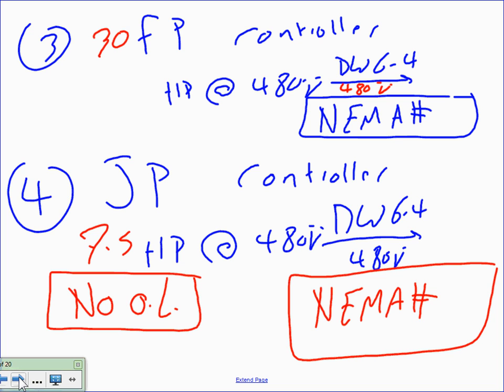Okay, let's go to number 3. Number 3, guys, we need the controller. And again, these numbers correlate with the sheet that you guys have. Everybody knows that. We have a 30 horsepower. We need to find the controller. To find the controller for 30 horsepower, we size controllers, guys, from number 3, you go to Article 430, which will tell you which reference leads you to the controller. You always size them based on the horsepower and the volt amp.